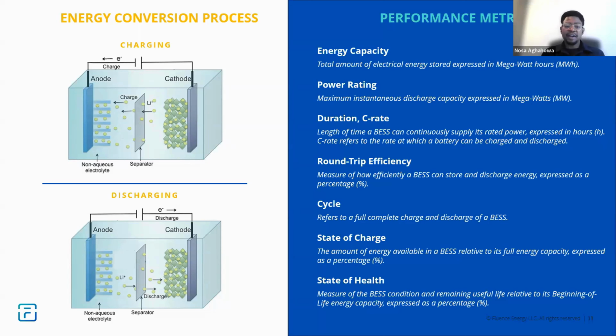A couple of metrics used to describe battery performance: energy capacity is the total electrical energy stored in the battery, expressed in megawatt hours or kilowatt hours. Power is the instantaneous discharge capacity, expressed in megawatts or kilowatts. Duration is the length of time the battery can continuously supply its rated power. The C rate is the inverse of the duration, the speed at which the battery can be charged or discharged.